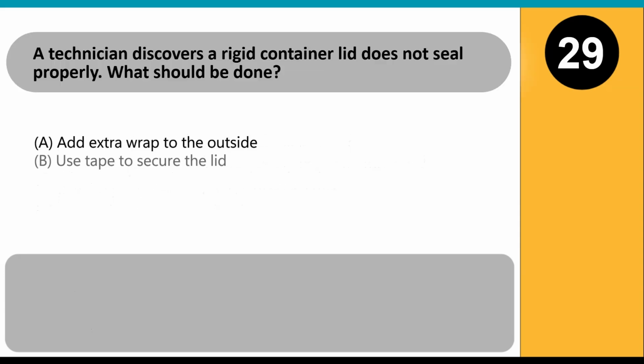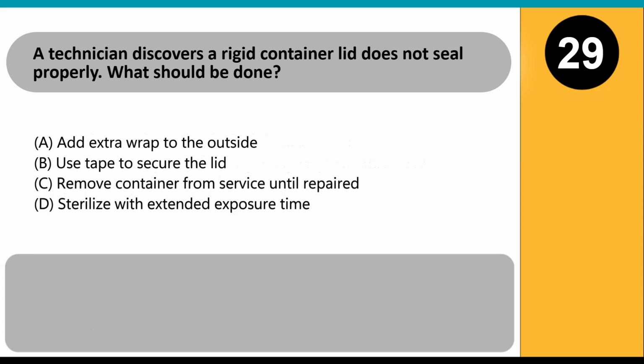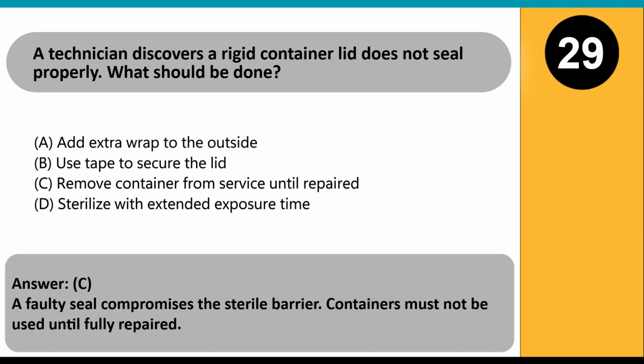A technician discovers a rigid container lid does not seal properly. What should be done? A. Add extra wrap to the outside. B. Use tape to secure the lid. C. Remove container from service until repaired. D. Sterilize with extended exposure time. Answer C. A faulty seal compromises the sterile barrier. Containers must not be used until fully repaired.